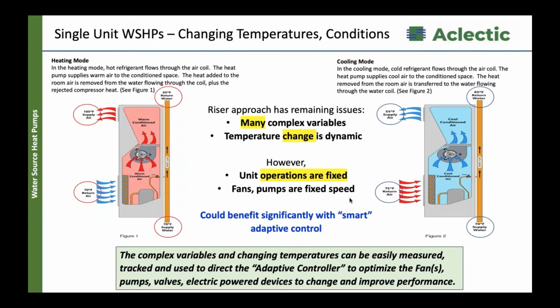However, what happens to that air is supplemented by the water running through the water source heat pump. That pipe on the right sees an incoming water temperature different than the outgoing water temperature, and on the right you see a similar thing. But what's affecting that water temperature? It's the return air in blue, the amount of air being pushed across it, where it is in the loop, the moisture content, and how much outside air. When you look at it, there are numerous things that interact with what's happening inside that little box.